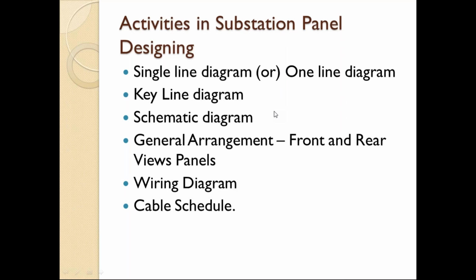This is nothing but a brownfield substation. We need the SLD, KLD, schematic, general arrangement, wiring diagram, and cable schedule; these already exist, but for that particular area we will go and modify them and produce the drawings. So there are two types: greenfield and brownfield substations. Greenfield means a new fresh substation, and brownfield means an existing project already there, where maybe we will replace something or extend one more bay depending on the load. These are the two types, and we get the project accordingly.